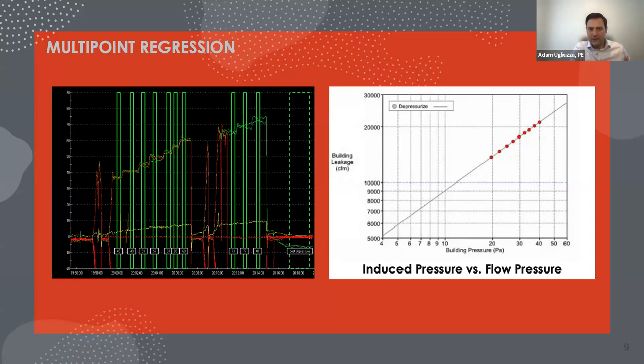Like if a door wasn't set to latch properly, it could fly open and you would get the repeated results. You'd get the same CFM leakage because that door would fly open the same way every time you did that at that test pressure. The multi-point regression allows you to see, as you go up the test pressure, if something changes, like a door opens, you're going to see that data. It's going to be a step in the data points. So you're going to say, something's not right. I've got to stop the test. I've got to check my test boundary because something's not right. But when you have a small test specimen, like a room, a single point method can be effective because you have visibility to that entire test specimen.